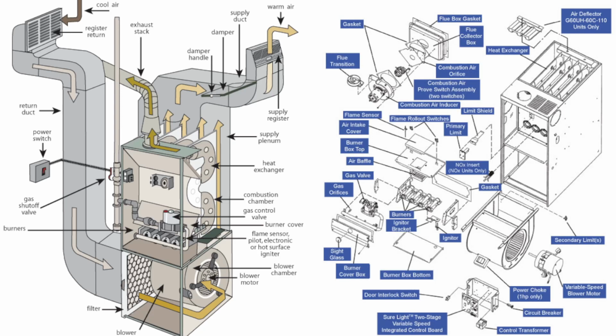Down below, you'll see the blower motor and the blower chamber. This combination, we call it the squirrel cage. That's just the terminology we technicians use out in the field, but that's the complete housing of the blower motor. If you take a look at the edges, you'll see the little mounts where the motor is held. There are rubber mounts there to help stabilize vibration so it doesn't shake. You will notice sometimes in some homes the weights on the blower itself will be unbalanced, and it'll actually vibrate, and it can damage the squirrel cage and/or the motor itself.